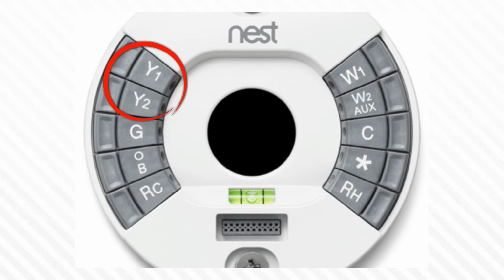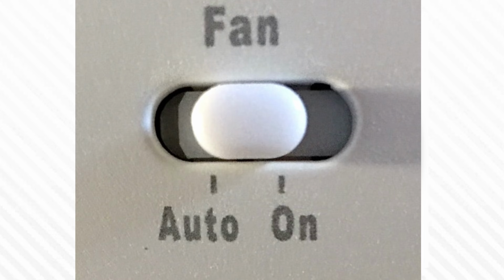Now, the Y1, Y2 terminals are pretty straightforward. Most people don't have any issues with these, so I'm not really going to get into that one here. If you do have any questions, just comment below, I'll answer. The G terminal is also pretty straightforward, but I do get a lot of people asking if they can use that as a substitute for a common wire if they don't have an extra wire available. That G wire typically serves two main purposes. Number one, in cooling mode, the thermostat will activate that G wire to turn on the blower motor in the air handler. Another purpose is that a lot of thermostats have a setting for the fan to turn it from auto to on or circulation.